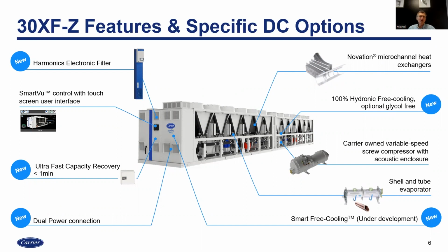Just to mention some of them: we have integrated what we call a harmonics filter up front, or you can call it a THDI filter - total harmonic distortion filter. These products by nature have variable speed compressors, which is the latest compression technology. But when you apply a lot of variable speed compressors, you can have an impact on power line quality, so you need specific filtration elements to reduce distortion that may affect other elements in the same distribution network.